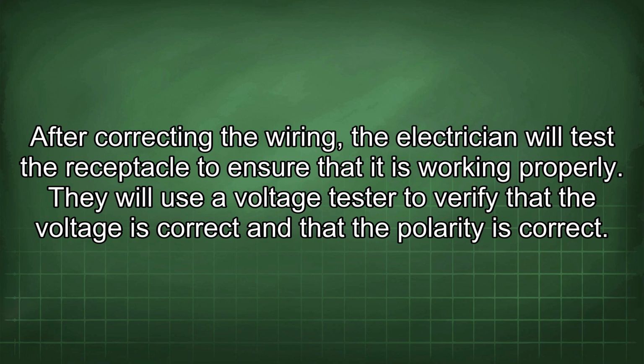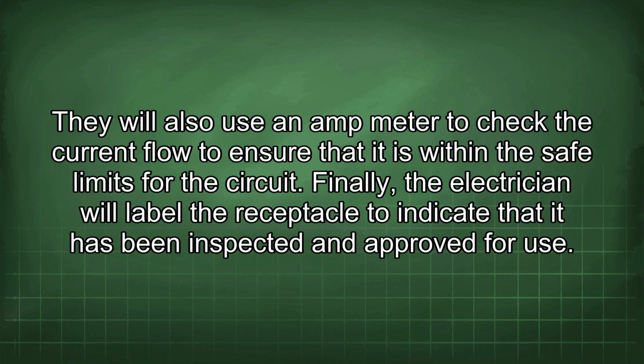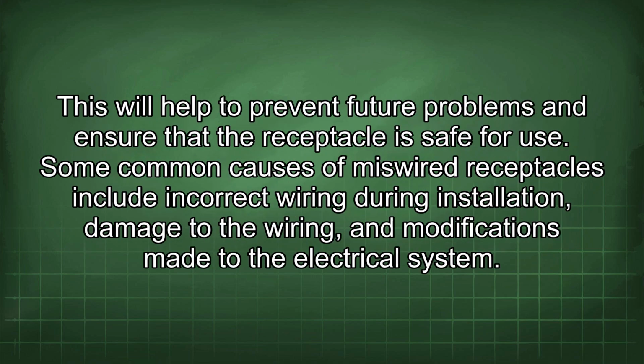They will use a voltage tester to verify that the voltage is correct and that the polarity is correct. They will also use an ammeter to check the current flow to ensure that it is within the safe limits for the circuit. Finally, the electrician will label the receptacle to indicate that it has been inspected and approved for use. This will help to prevent future problems and ensure that the receptacle is safe for use.